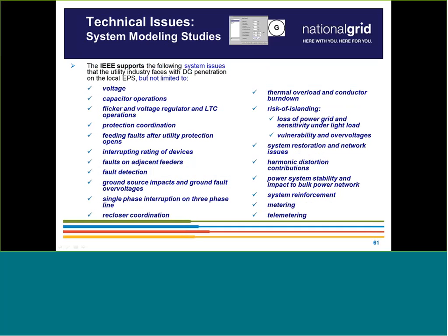This is a longer list of potential impacts — some are more common than others. A lot of the time, fault detection can be an issue, along with ground source impacts and ground fault overvoltages, which is really an effective grounding issue.